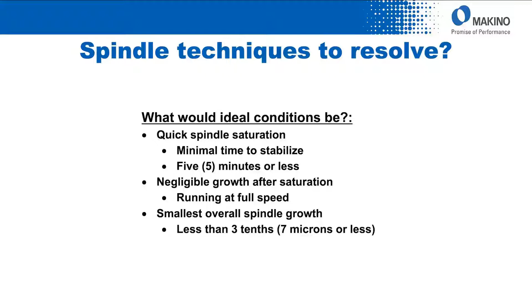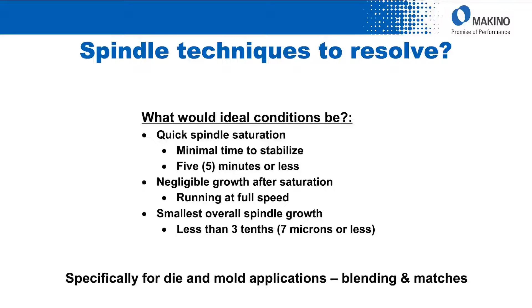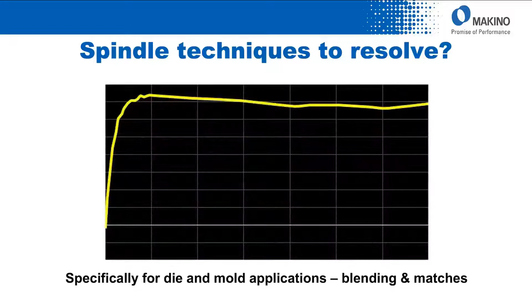What would typical ideal conditions be? Well, I'd like a quick saturation, minimal time to stabilize. Once it gets there, I'd like to run at full speed and have very minimal growth. And I'd like the overall to be 7 micron or less. That's especially important if you're doing die mold, where you're doing matching and blending and things like that. So that's what I'd like to see.